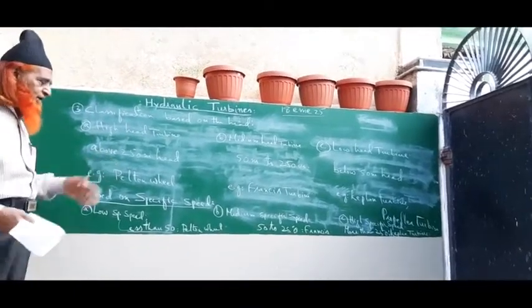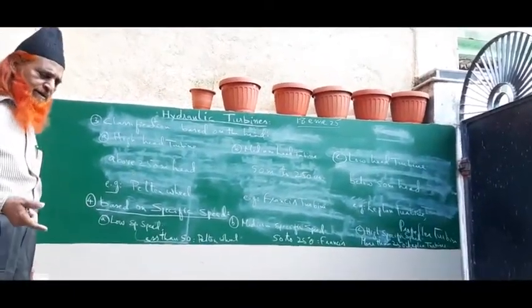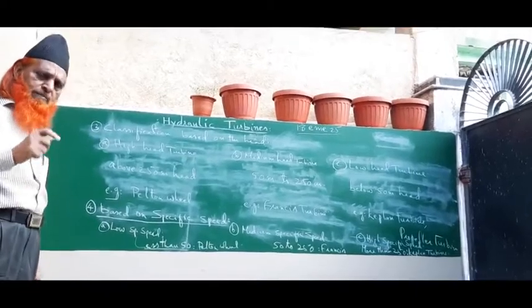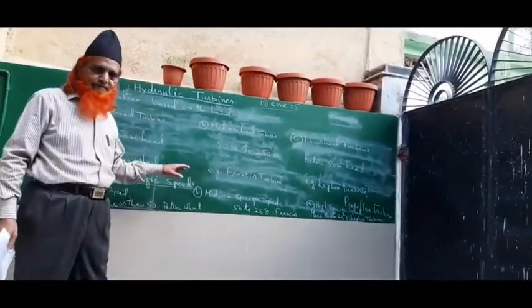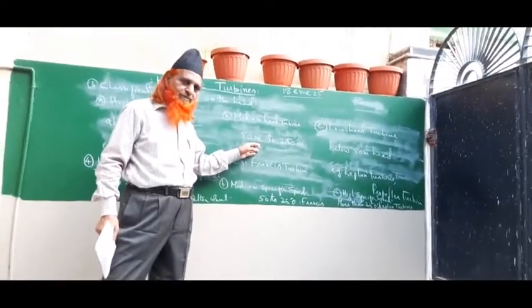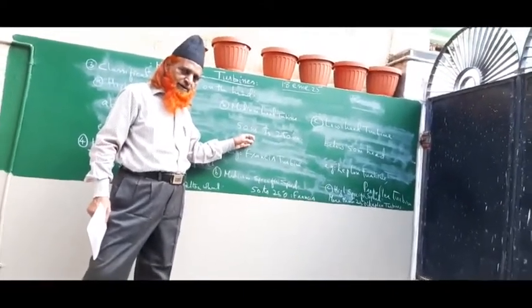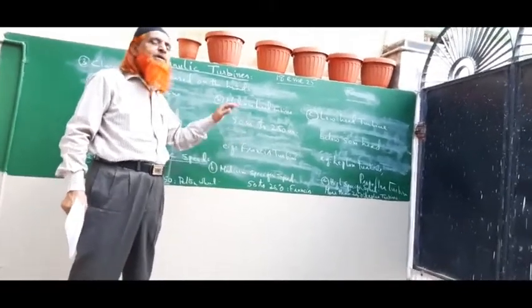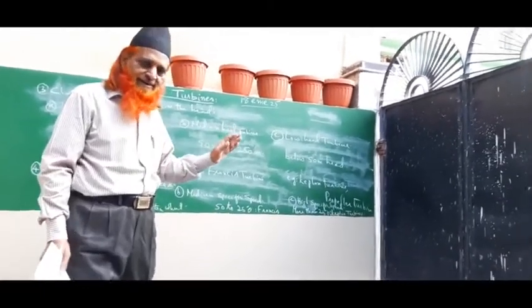I want to talk about the Pelton wheel separately, Francis turbine separately, Kaplan turbine separately. We are going through that anyhow. Therefore, is it clear to all of you? Therefore, a Francis turbine will be a radial inlet with an axial outlet, and it is a medium head, medium specific speed turbine, and head is also 50 meter to 250 meter, and specific speed also 50 to 250.